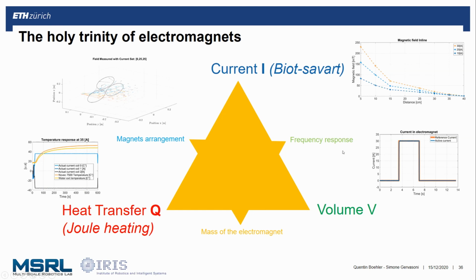In addition, you also have things like frequency response. Very large coils with a lot of windings have very poor frequency response, meaning you can't change the field direction quickly. Then there's the mass of the electromagnet—remember I mentioned how heavy the system can be to actually be carried around. If it's too heavy, you might actually fall through the floor. And the magnet arrangement can play a huge role, like this triangular arrangement we used here.